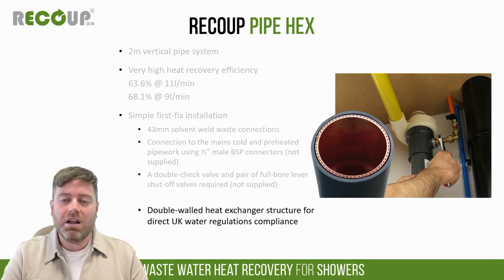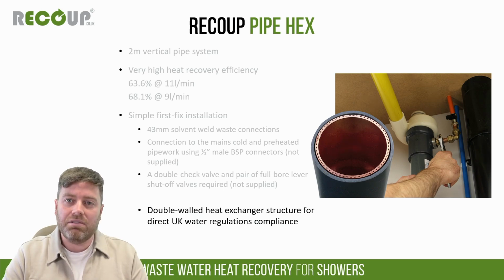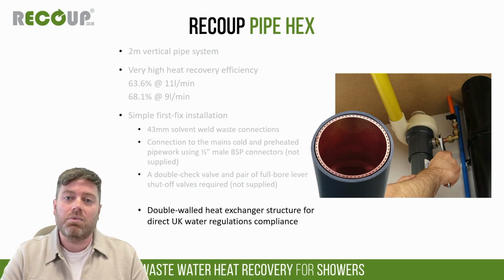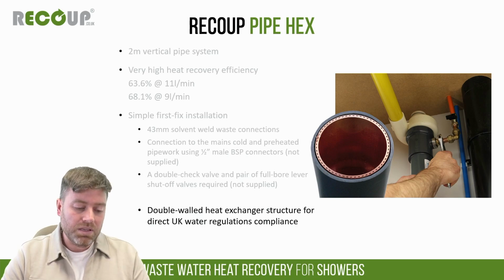You might be able to see on the cut through of the pipe there, that's one of the pipes which has been cut through. There are some small striations around the top of the pipe, and those striations run the whole length of the pipe. So if there was ever to be a puncture or anything of the heat exchanger, we'd get visible leak detection at the bottom, because the water would run the length of those pipes and drip from the bottom of the pipe, and we'd get a detection at first fix and pressurization. In practice, we've never actually had one leak, because they're all pressure tested before they leave the factory, and they can be pressure tested up to 10 bar on site if need be. But in practice this never happened, but we do have that leak detection system there, and that double wall heat exchanger construction as a sort of belt and braces method to compliance.